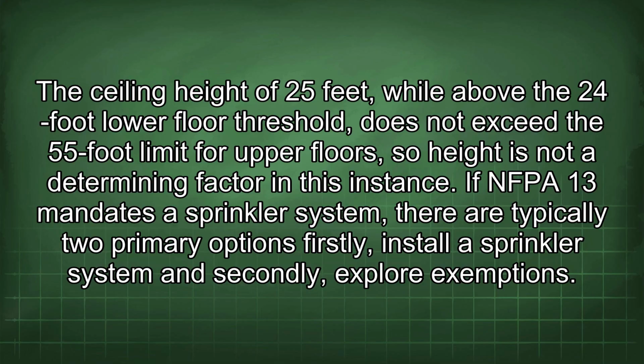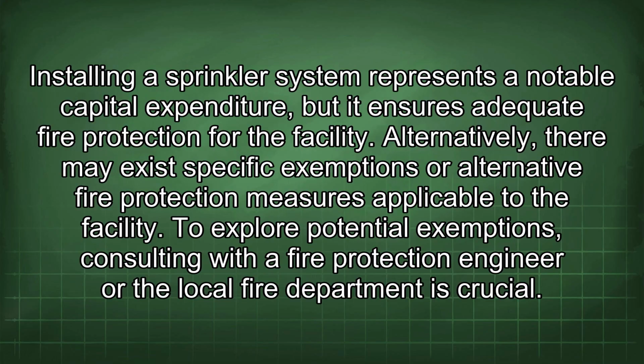If NFPA 13 mandates a sprinkler system, there are typically two primary options. Firstly, install a sprinkler system, and secondly, explore exemptions. Installing a sprinkler system represents a notable capital expenditure, but it ensures adequate fire protection for the facility. Alternatively, there may exist specific exemptions or alternative fire protection measures applicable to the facility. To explore potential exemptions, consulting with a fire protection engineer or the local fire department is crucial.